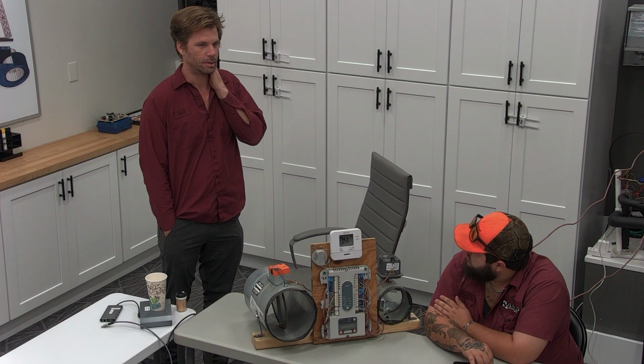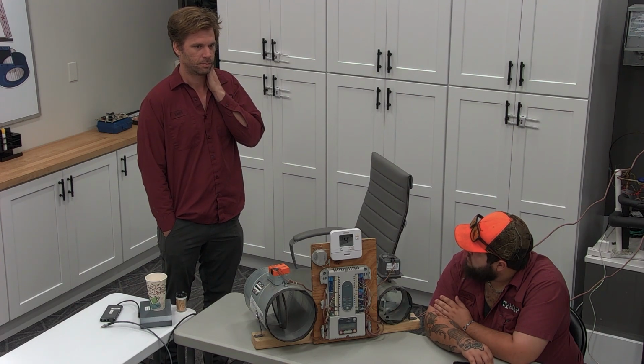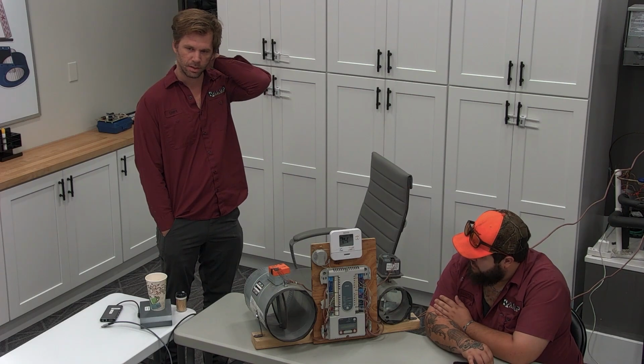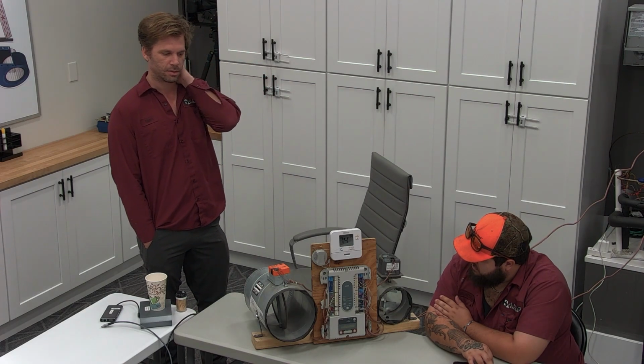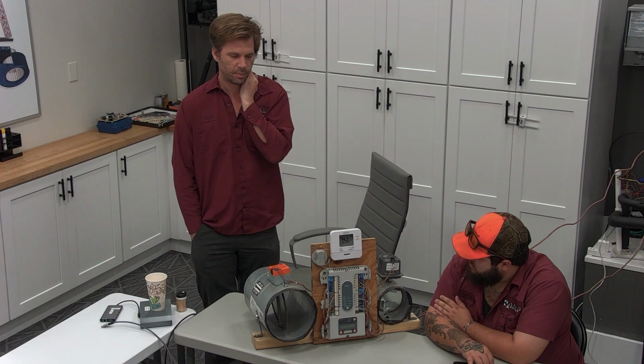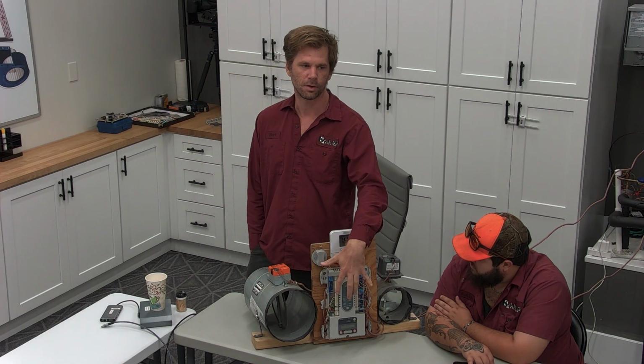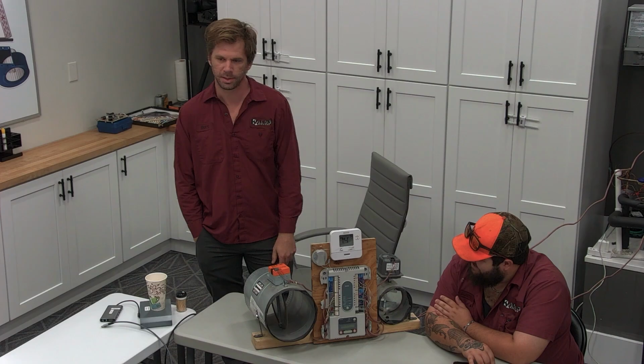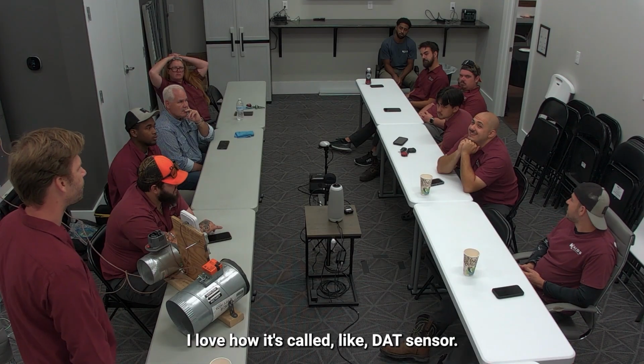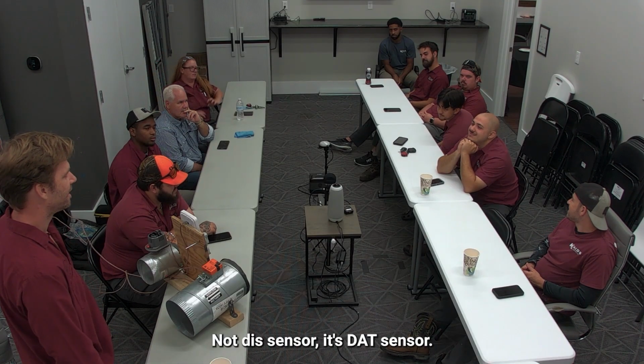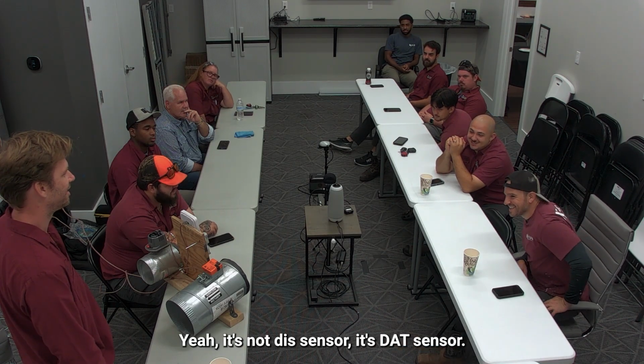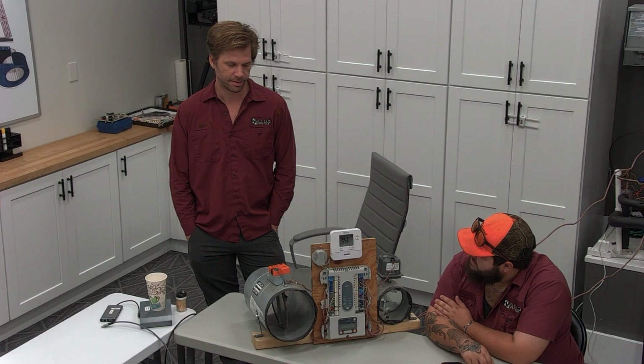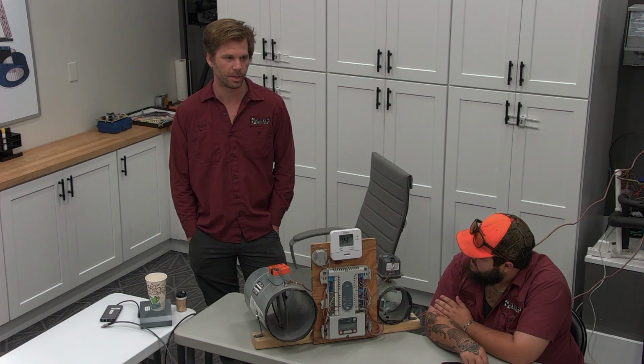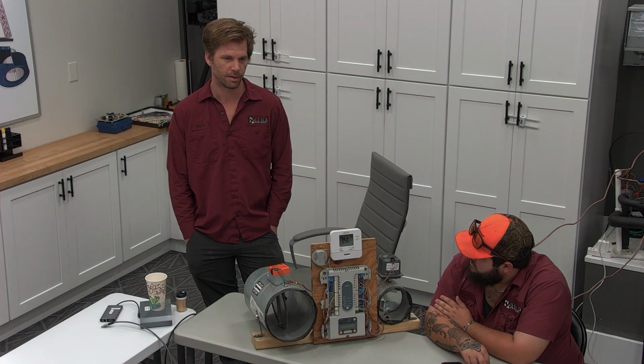We want to know that's the only problem there, right? And that's the only thing they're dealing with. So when a DAT sensor is an issue, you can simply unplug it. The board will blink at you in frustration constantly, but operation will still be there. I love how it's called DAT sensor. Not this sensor, it's that sensor. Yeah, it's not this sensor, it's DAT sensor. That's exactly what it is. Yeah, it's an acronym that stands for discharge temperature. Nice, great. The limits typically are 45 and 155, preset limits.